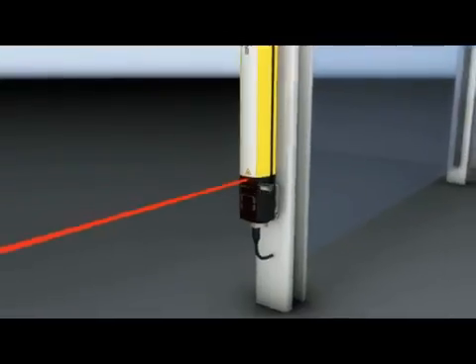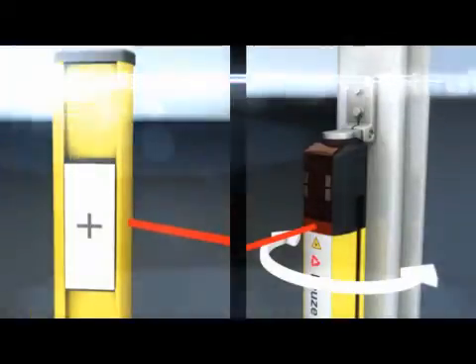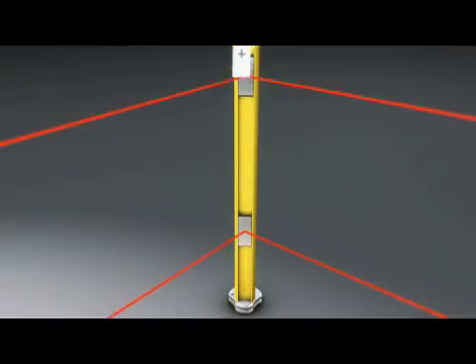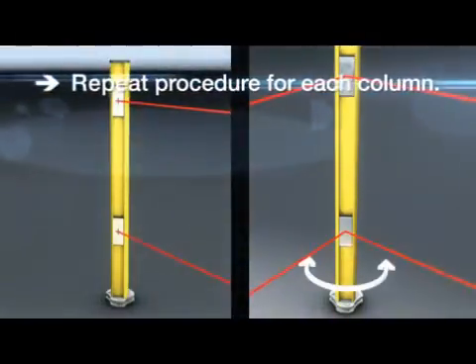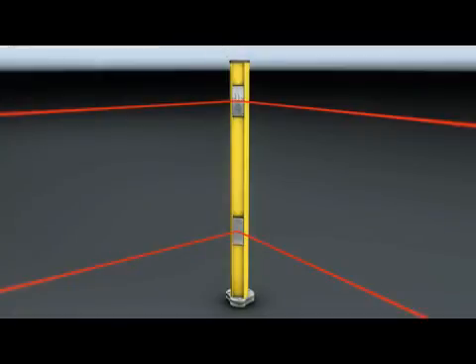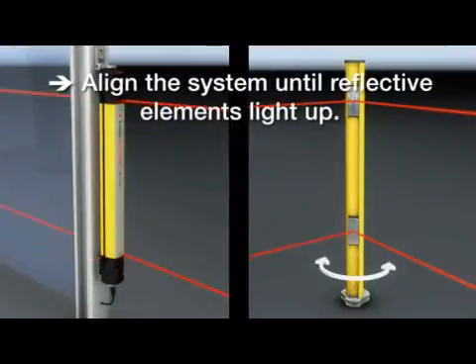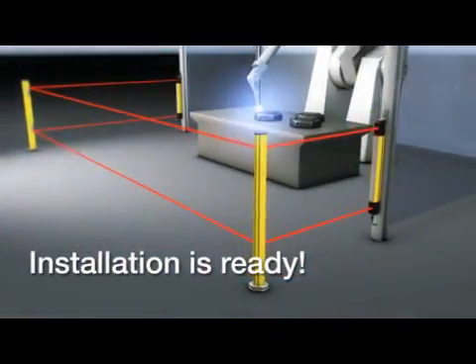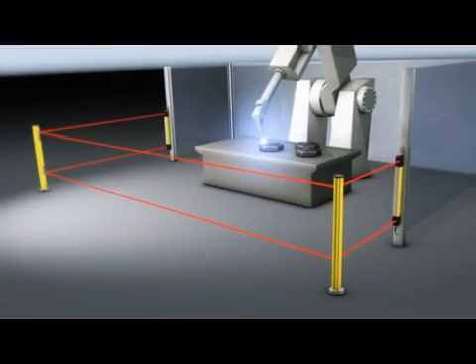Simply activate it with a magnet key, and direct the laser beam onto the template at the deflecting mirror column until the target has been hit. Step by step, each deflecting mirror column is aligned and adjusted. Finally, it's the receiver's turn. When the integrated reflective element lights up brightly and visible at a distance, the installation is complete. That's typical for Leuze electronic MLD — alignment doesn't get easier than this.